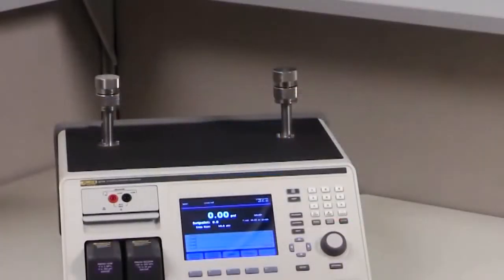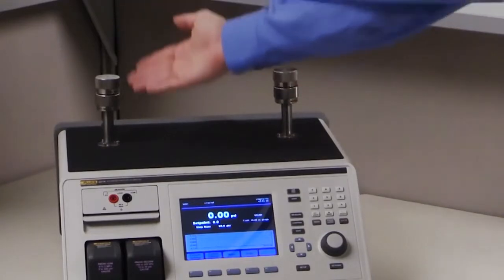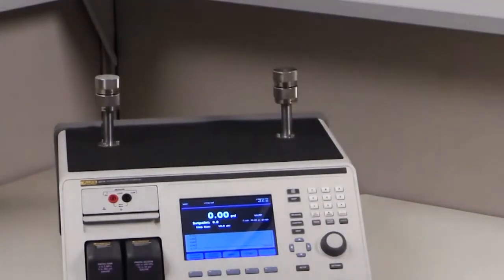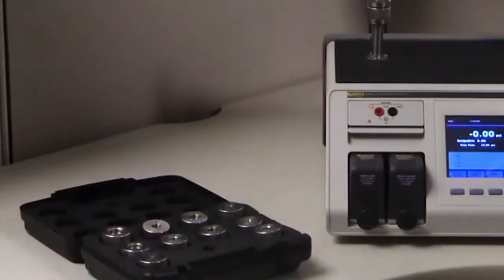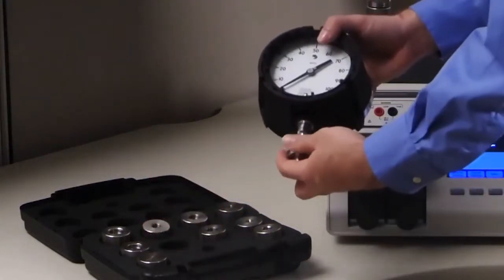To test a pressure gauge, connect it to one of the two vertical test ports on top of the 2271A. The 2271A comes with a number of adapters to connect to common NPT, BSP, and metric sizes.